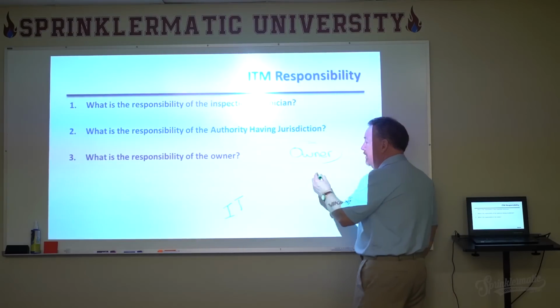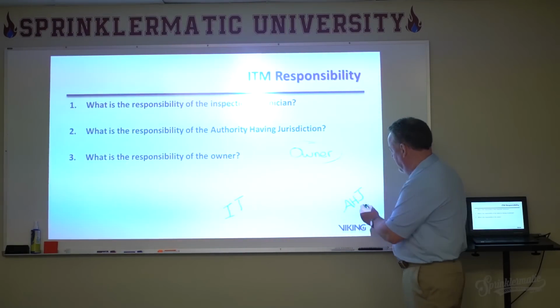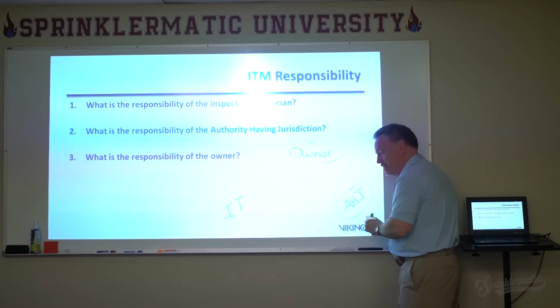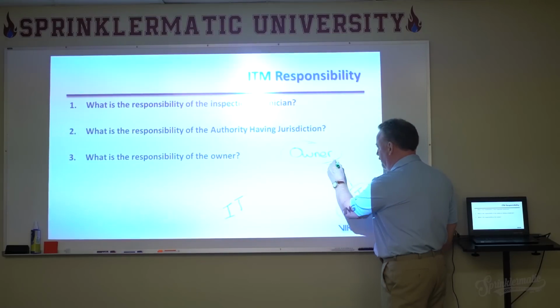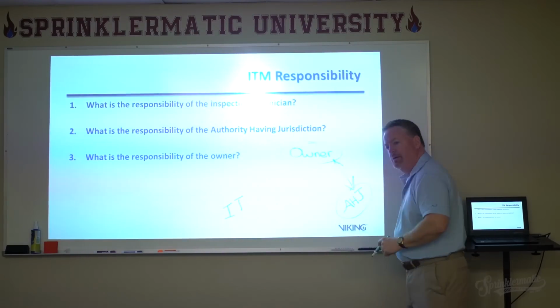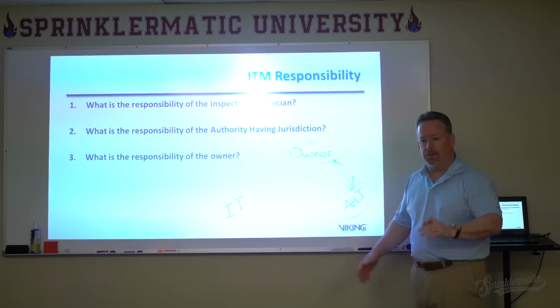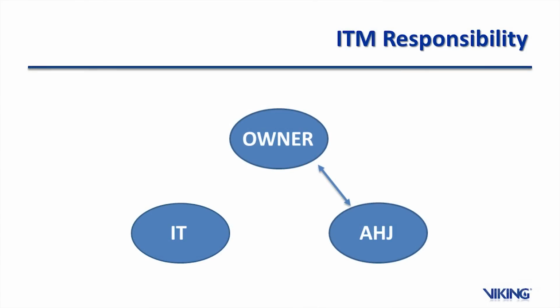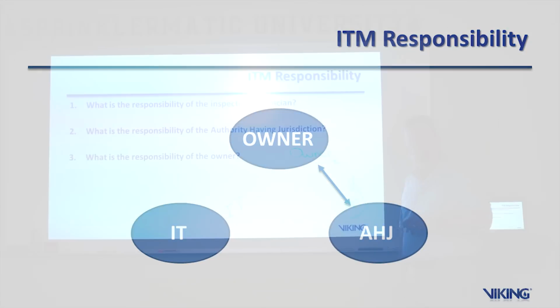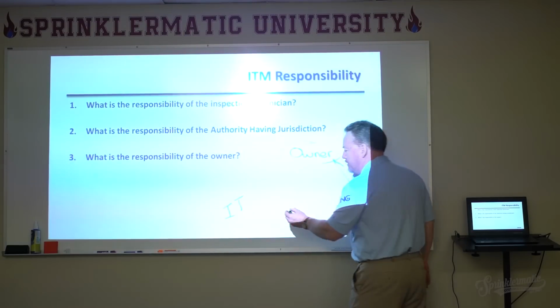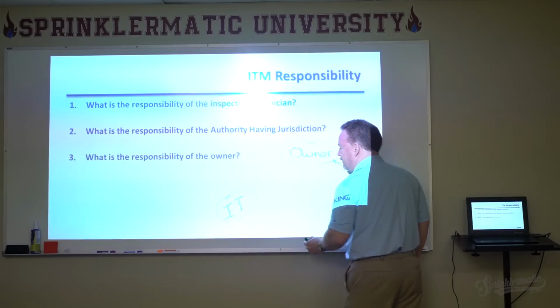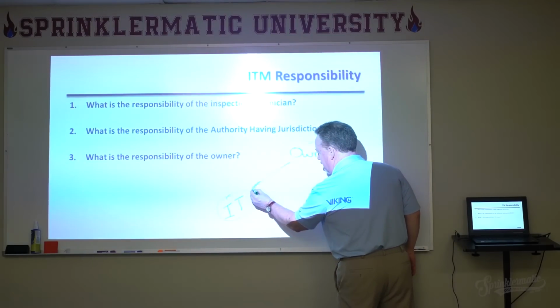They know it does something, and they've seen it in the movies that a bunch of water comes out, and they hope to God it never happens in their building. So they may or may not know a whole lot about your system in that building. So what do they do? They say, well, my gosh, the AHJ has adopted a law that says I've got to comply with NFPA 25. How am I going to do that? Okay, well, there's a contractor out here that does inspection, testing, and maintenance. So we go with the contract.